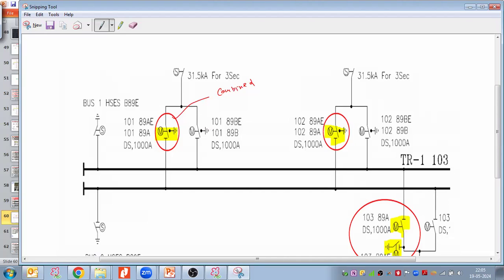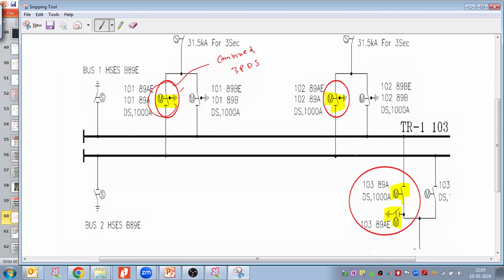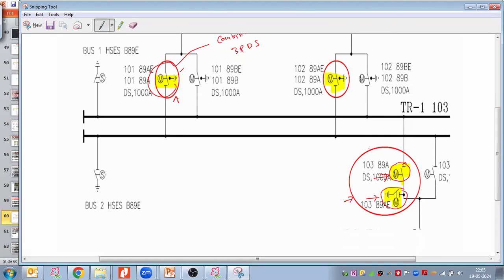When you prepare the SLD with this arrangement, is it making sense? And if you are taking both in separate modules, then prepare the SLD with this kind of arrangement. This is our isolator module, and this is our earthing switch module. At the time of SLD preparation, we have to indicate what kind of disconnector and earthing switch we are taking, particularly in the GIS SLD submitted by the GIS manufacturer. In that SLD it should be clearly indicated, because the GIS manufacturer is going to provide the GIS module, so they will take a call on which kind of arrangement they are going to propose.